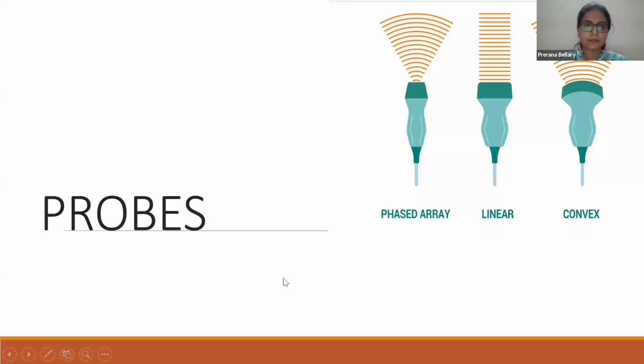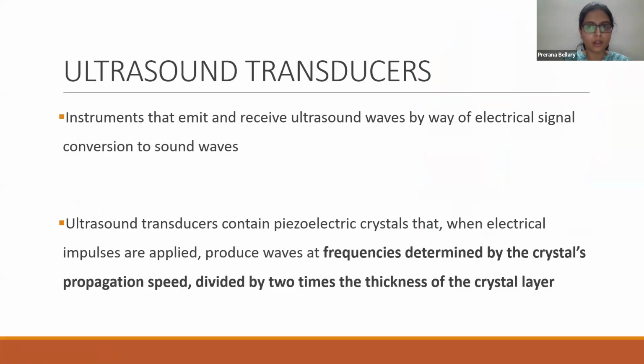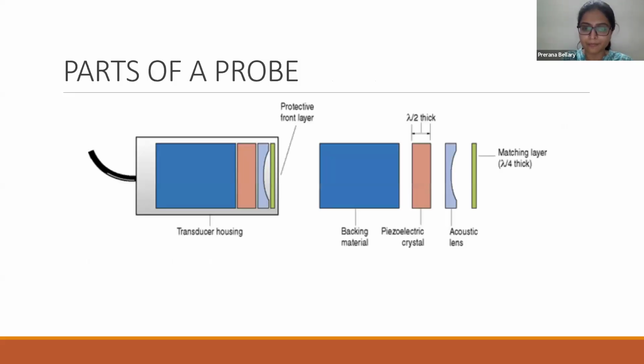Now coming to probes. Ultrasound probes or transducers, what are they? They are instruments that emit and receive ultrasound waves by way of converting electrical signals to sound waves, right? Ultrasound transducers contain piezoelectric crystals. When electrical impulses are applied to them, they produce waves. What is the frequency of this wave? That is determined by the crystal's propagation speed divided by the thickness of the crystal layer. So the frequency will be decided by the denominator. If the thickness is more, the frequency will be less, and if the thickness is less, the frequency will be more.